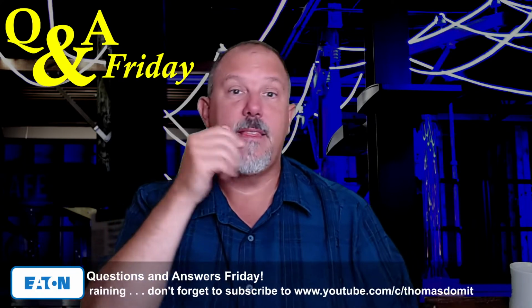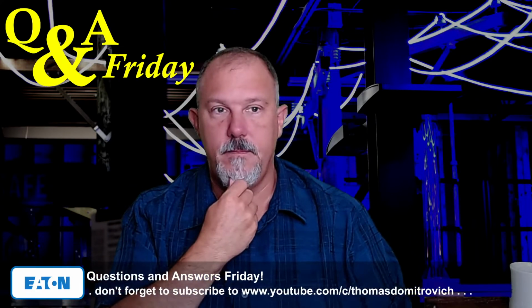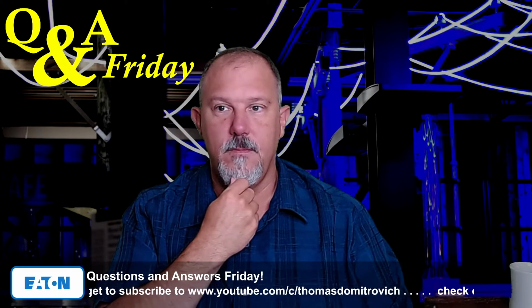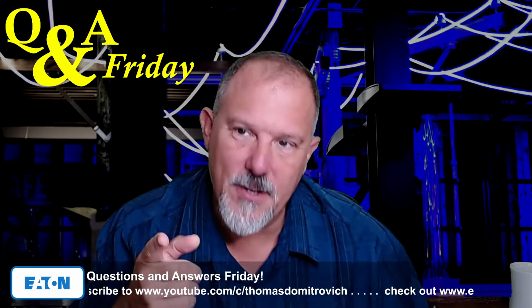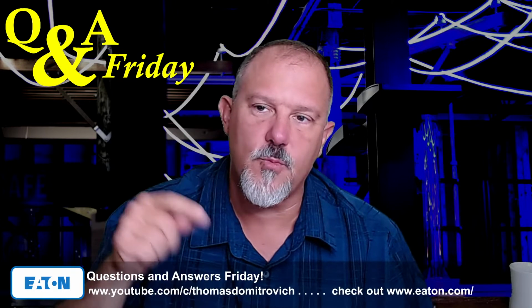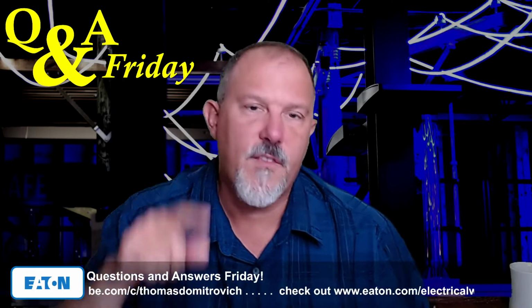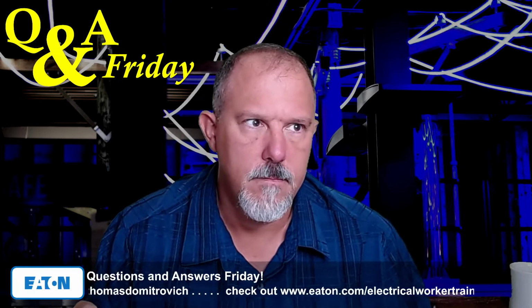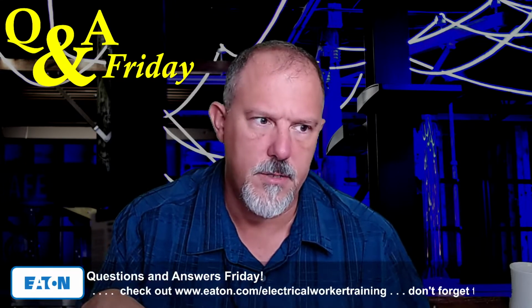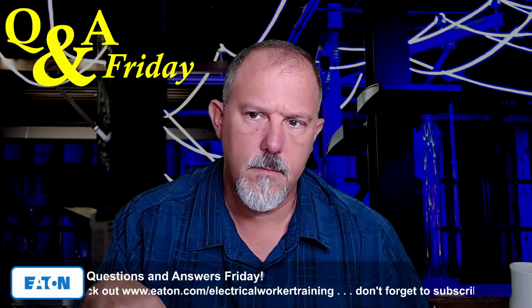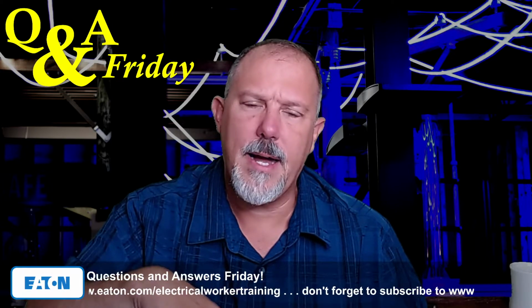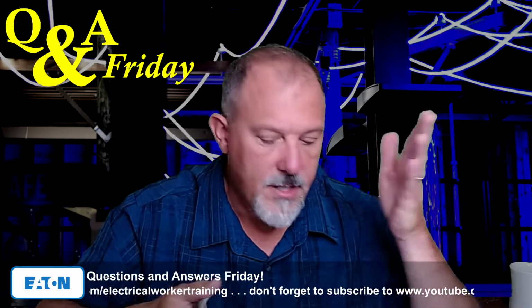I think I know what you're talking about. Circuit breaker is set on locked rotor. So if you're thinking about a fire pump, 240.87, there's no exceptions in here for fire pumps. So no, I mean, here's the thing, Al.